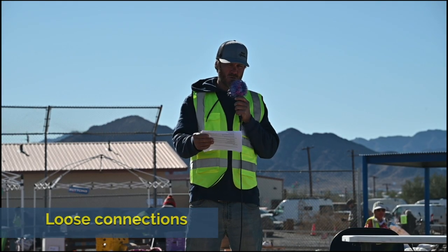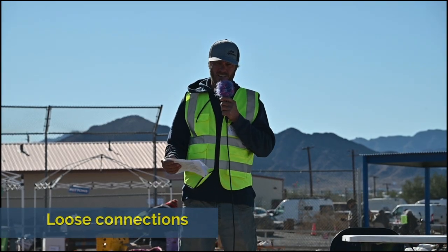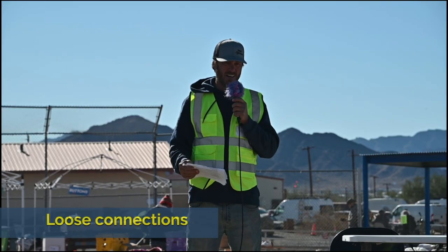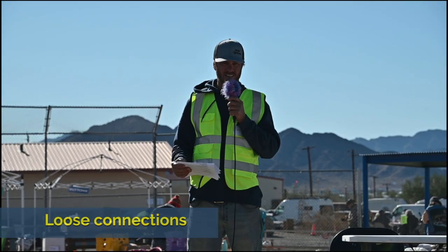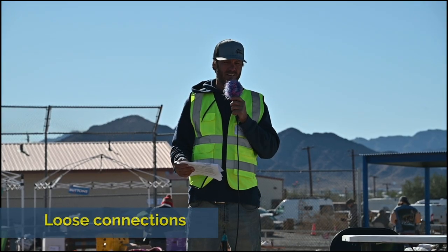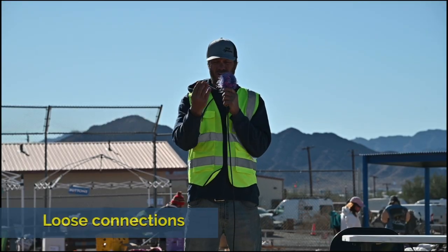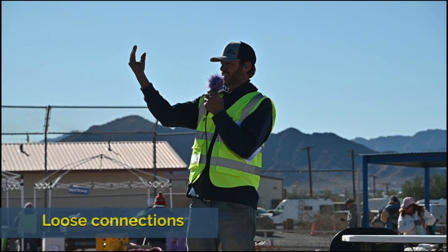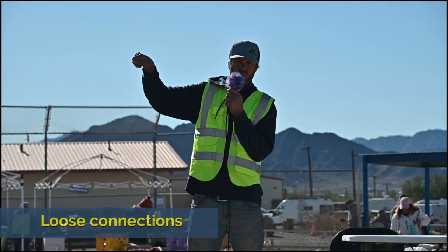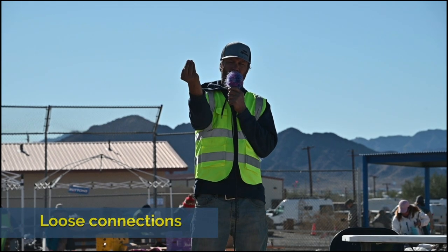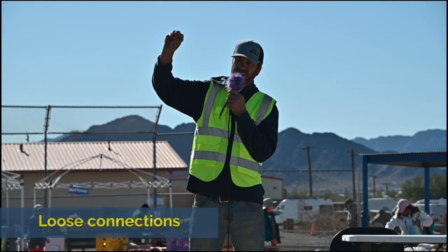Poor crimping and loose connections. That's actually, in my opinion, one of the major causes of fires: a loose connection. It creates heat. That heat will create a fire. It's going to happen. If you have your charge controller hanging on your wall like this, and you've got wires stuffed in the bottom of it, and you've clamped them as tight as you can with that screwdriver, those wires get flat, and it's copper.